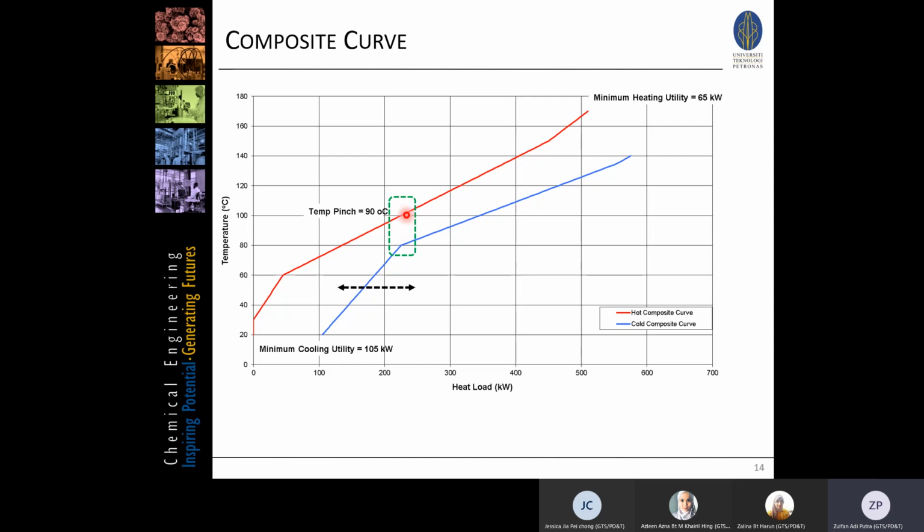But the concept is that the pinch temperature is the temperature at which the 2 curves are at the closest. If we allow them to be as close as 20 degrees C, this is going to be the result. So this 20 degrees C, or the delta T min selection, is important. I think that Jem guy from KBR has mentioned the impact for 3 different delta T. But we will see that later on.